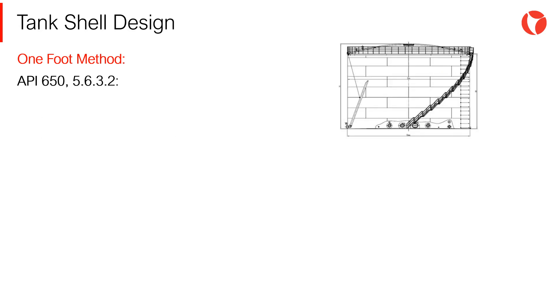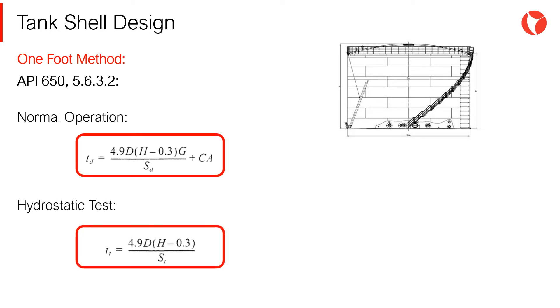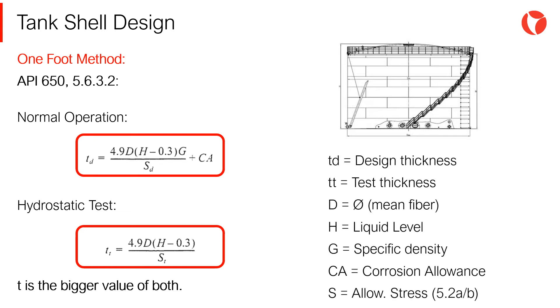The tank shell thickness calculation, according to the 1-foot method, compares two load combinations: normal operation loads and hydrostatic test loads. The bigger value of these two will be adopted for the tank shell thickness. This thickness is a function of the mean diameter of the tank, the liquid level, the specific density of the fluid, the corrosion allowance if required, and the allowable stress.